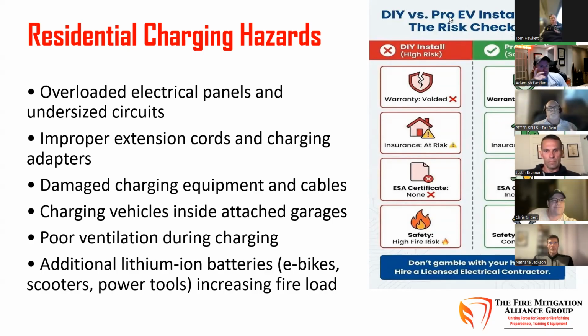Overloaded electrical panels, improper extension cords, damaged charging equipment and cables, poor ventilation - that's another big one. When these gases build up inside these modules, even in a garage, with an EV going into thermal runaway, the explosion hazard from the toxic, flammable gas is real. Many people don't know that if it's not ventilated properly and it builds up behind the door box of a charger or inside a garage, the explosion hazard is the real risk, not just the fire itself, because it's not ventilated.